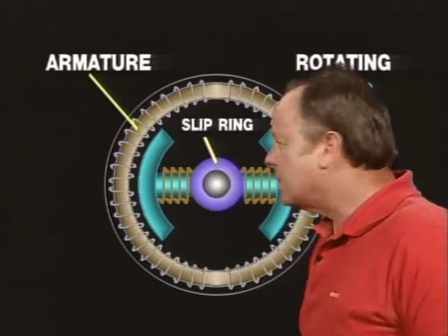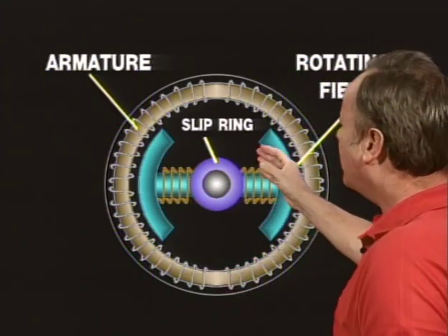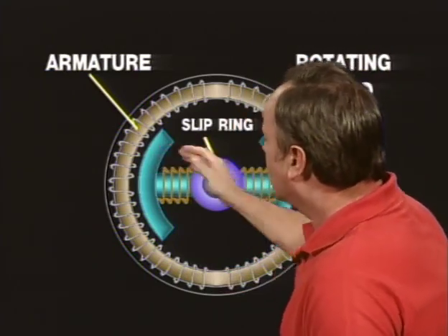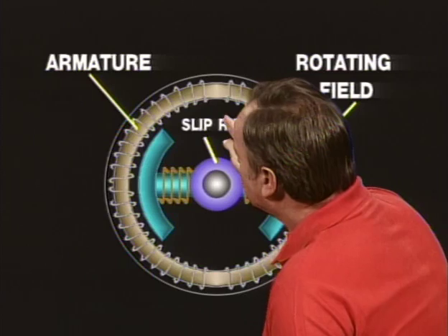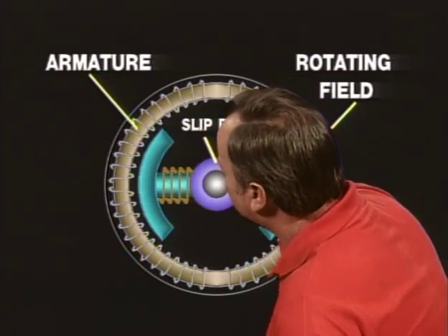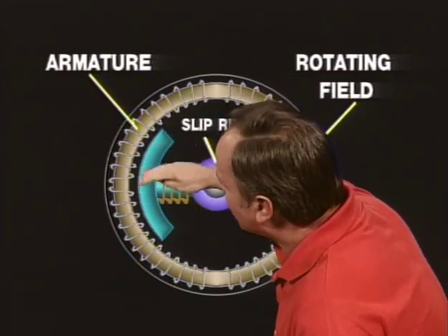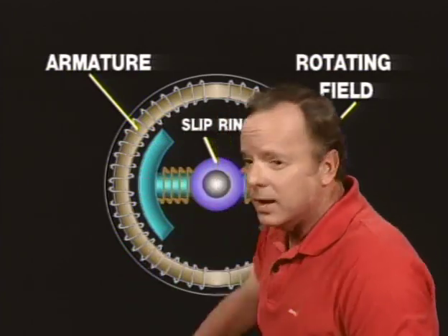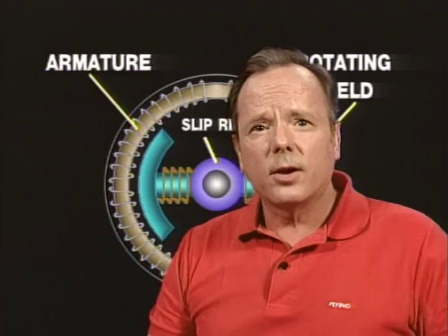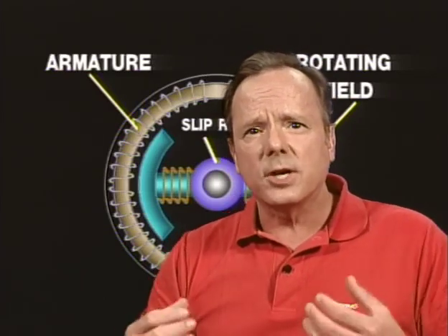And what happens is, of course, the field goes by these windings and produces alternating current, and the frequency of that current depends on how fast this generator rotates. The faster it rotates, the faster the frequency will be. Well, if you have, we'll say, 3 alternating generators going at once, you want them all to be synchronized. In fact, you want them at the same frequency.